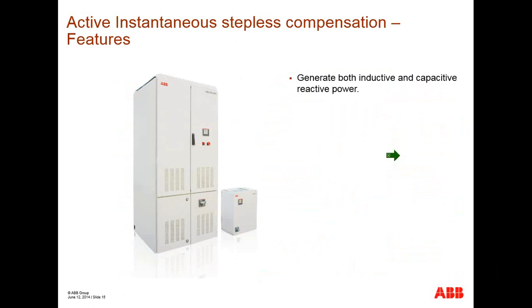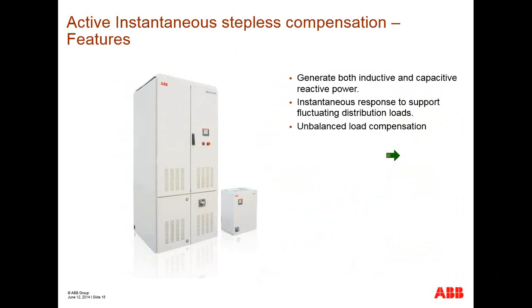Typical presentation which shows an active compensator, which, as I explained, can generate both inductive and capacitive power, with instantaneous support response for the fluctuating distribution load, and unbalanced load compensation. It is suitable for both low voltage and medium voltage, and can also be used with a step down transformer. It is a modular design. As you see, the number of panels can be increased depending on the required load, and they can all be connected through CAN bus.